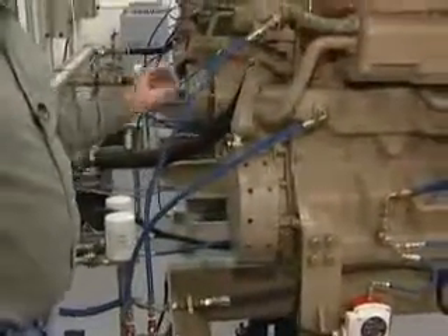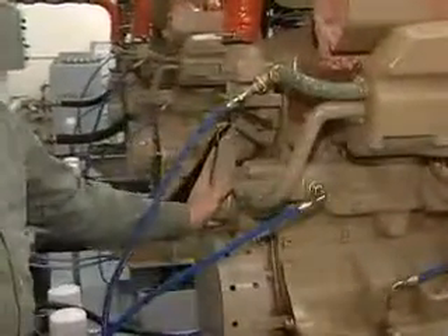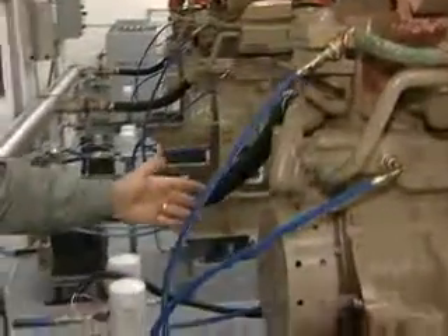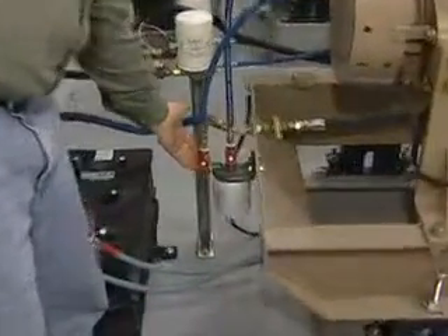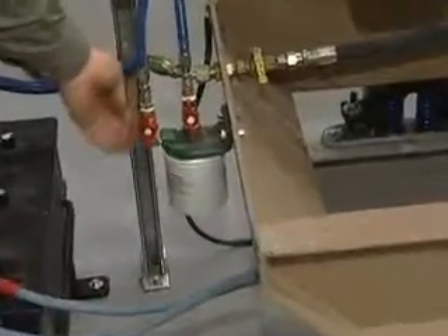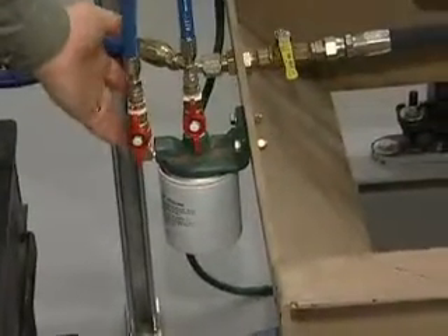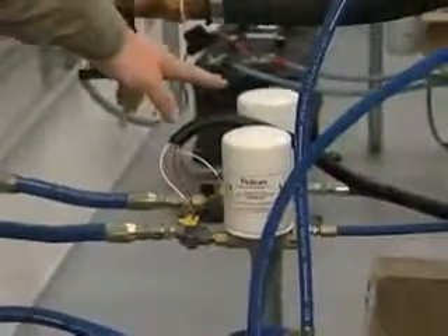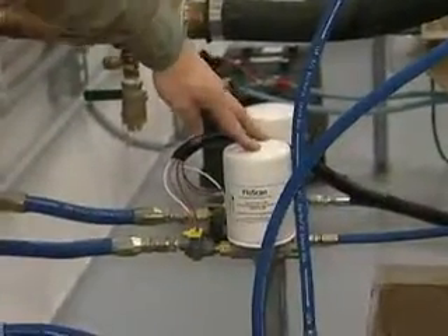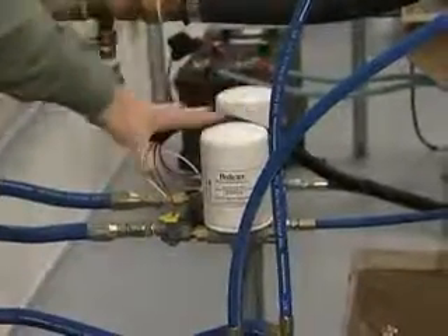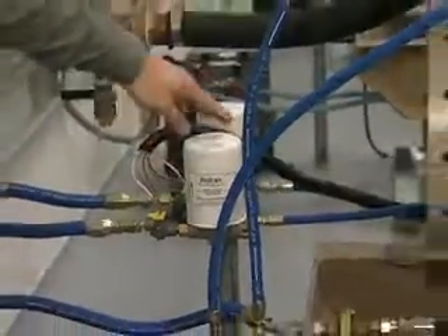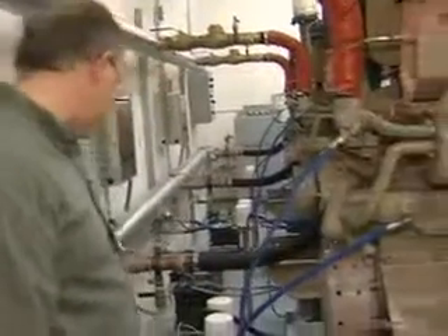Basically, any moving parts should have guards over them. Some of these have belt-driven water pumps on them. This one has a gear-driven water pump. It sits right here on the front of the engine. As we move down, we come down to here. This is a coolant filter, basically, that has valves on it so you can isolate that and change that. Some of our systems also have fuel flow sensors on them. That's what this device over here is. These are not filters. They do not have to be changed. These are a one-time item. Once we put this system together and put these on it, you never have to mess with these. They never have to be changed.